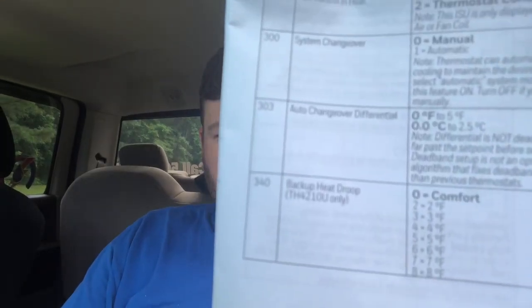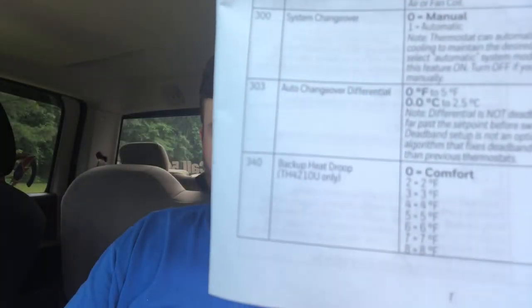Basically the auto changeover is a temperature range — we usually do three degrees. If the temperature gets above it, it'll bring on the AC; if it gets below that range, it'll bring on the heat. Here in Virginia there are some mild days where at night the heat comes on and during the day the AC comes on. Setting 303 lets you change that changeover differential range — you can go all the way up to five.